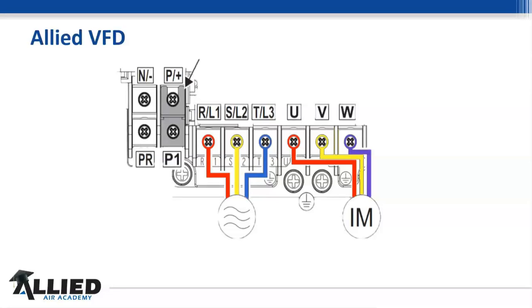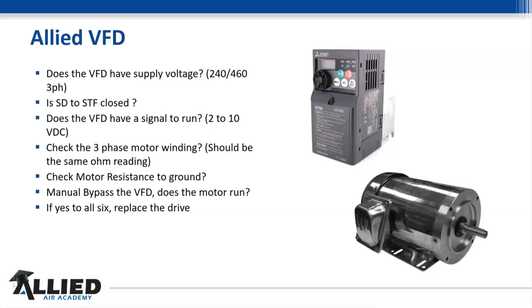If you get the voltage and the current up front, because all you got on the phase balance forgiveness-wise is 2%, and that's it. After 2%, the drive thinks the motor is in danger of burning up or messing up, and it's going to shut it down. And when you wire it, it's fairly simple. You got R, S, T or L1, L2, L3, and then you got the output to the motor. Now, this is already going to take care of the rotation of your motor, and we talked about that last week. You've got to go back and take a look at the compressors, but this will take care of the rotation of the motor because it's programmed in. It knows which way that motor should be turning. So if we got voltage in and we got voltage out, we know we're pretty well good to go, but there's also some other things, that other board in there, so we want to look at.